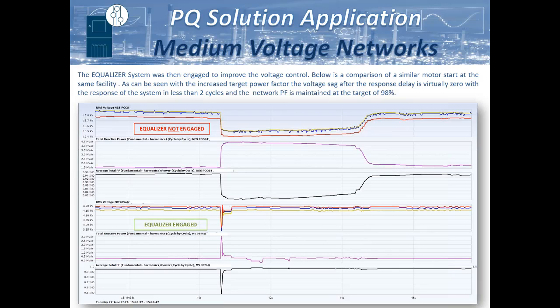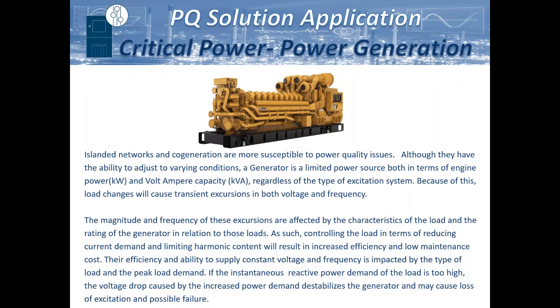So it's a very, very significant impact. It can also work. We're actually the only solution when it comes to either cogen or island networks, local generator power supply. Most manufacturers clearly state that any power factor correction system cannot be on the same network, with a caveat on our system.